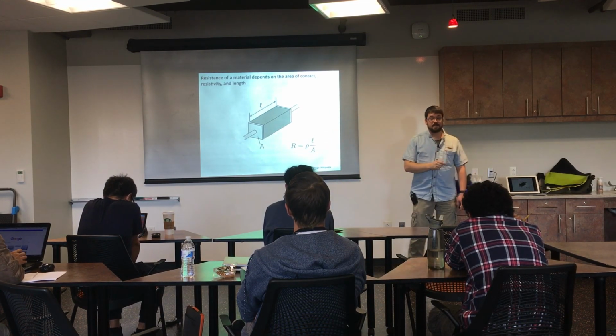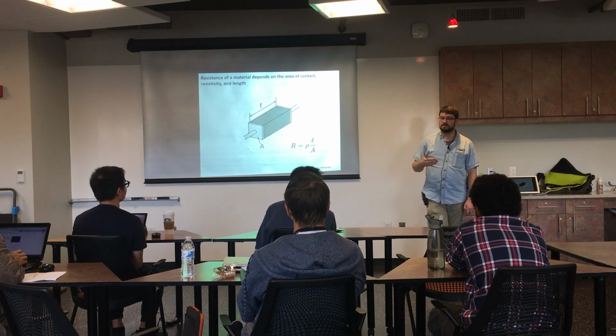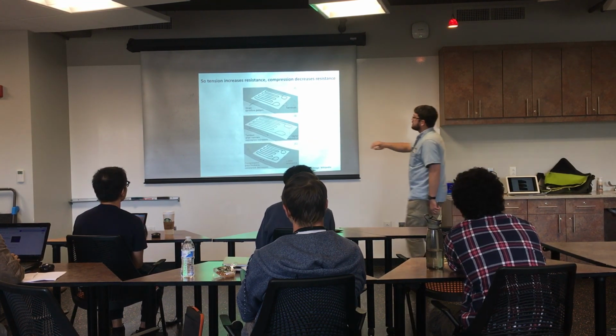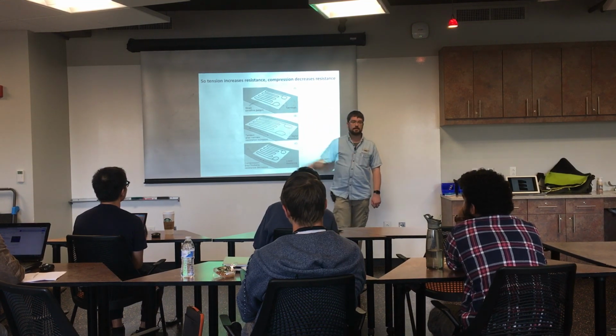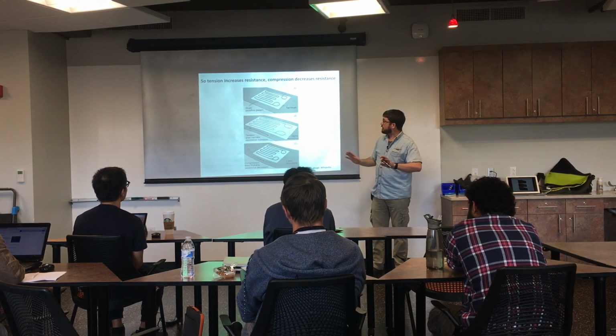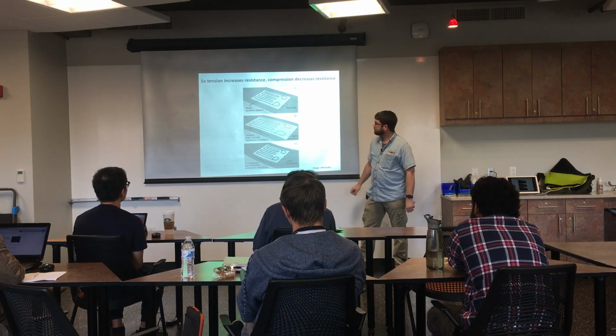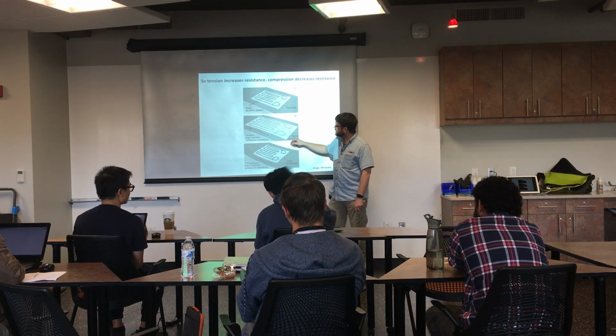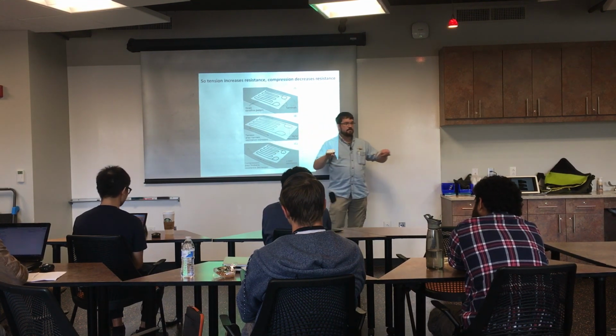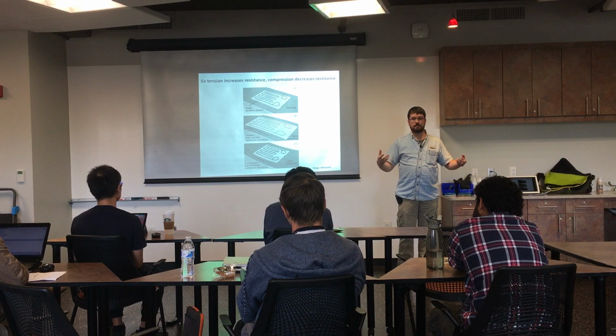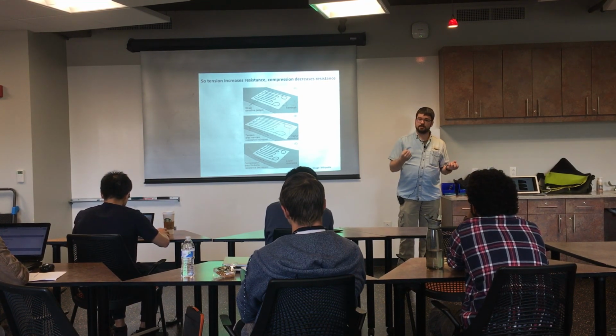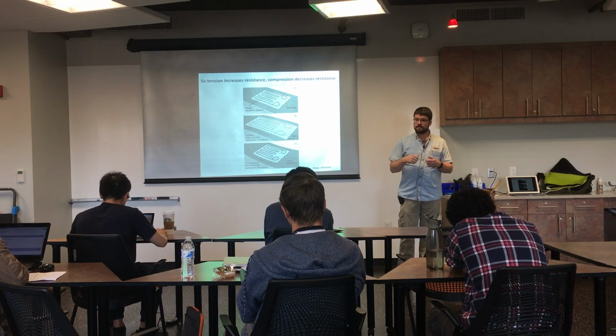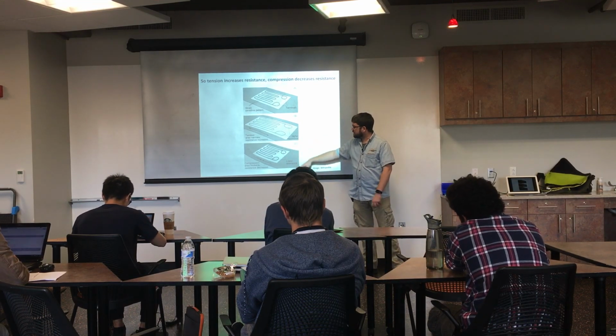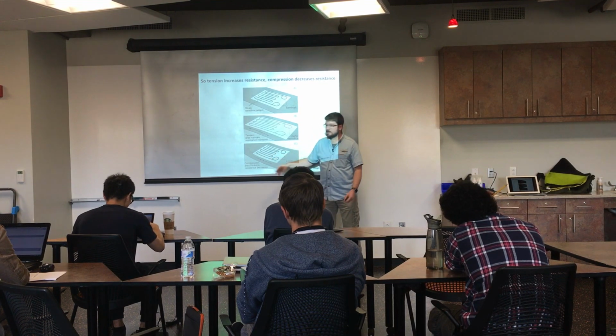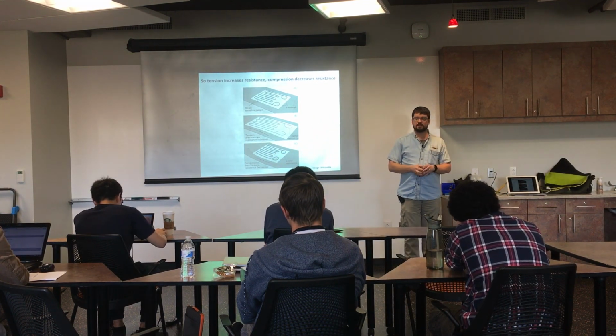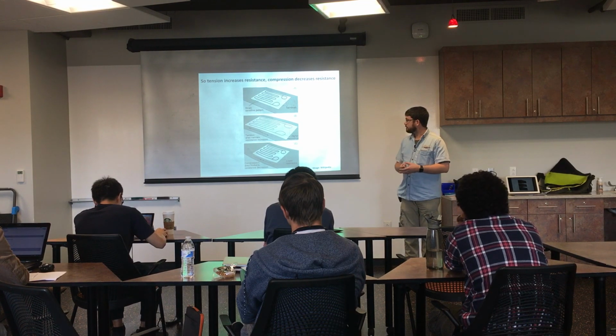So what we're going to change is that cross-sectional area in a strain gauge. It works like this: let's say this is the strain gauge stuck to your piece of rock or metal, and it's at rest, with no external strain. Now if we put this in tension, these little pieces of copper have to stretch out because they're being pulled apart. That means their cross-sectional area is reduced, which makes the resistance go up. So as you stretch it, the resistance becomes higher. In compression, the copper is compressed and bunched up, the cross-sectional area gets larger, and the resistance goes down.